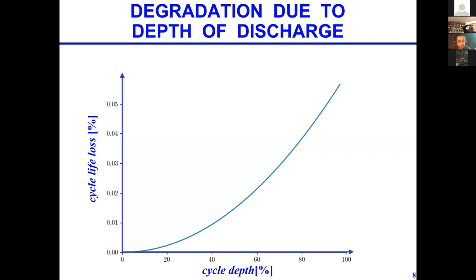But it's going to be a number, might be less than one. I'm making the situation easier for you. Let's assume we bought a battery which has 1,000 cycles. We're going to run 1,000 cycles, and every time I go to a cycle depth of 60%. So after 1,000 cycles, I'm going to lose essentially 0.02 times 1,000, which is 20%.